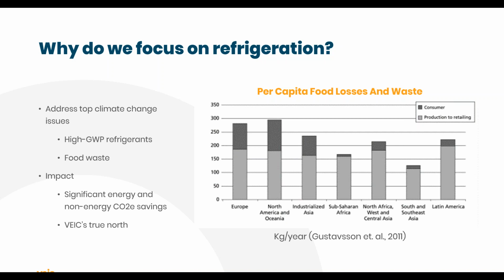First, all the refrigerants I've talked about are typically super pollutants. The refrigerants used today are hydrofluorocarbons, with global warming potentials 2,000 to 4,000 times higher than carbon dioxide. In layman's terms, 1 pound of a typical refrigerant, R404A, is equivalent to 2 tons of carbon dioxide emissions. So it's very important that the refrigerants we use stay in the pipes and don't leak into our atmosphere, and that we transition to lower GWP refrigerants, specifically natural refrigerants.